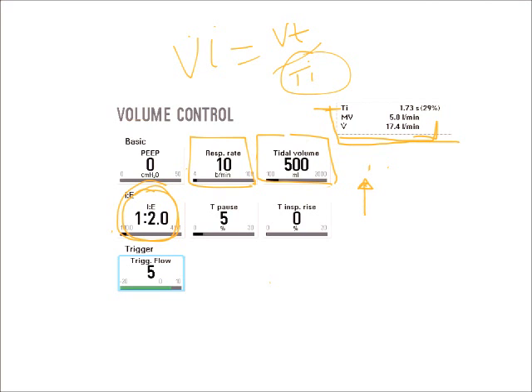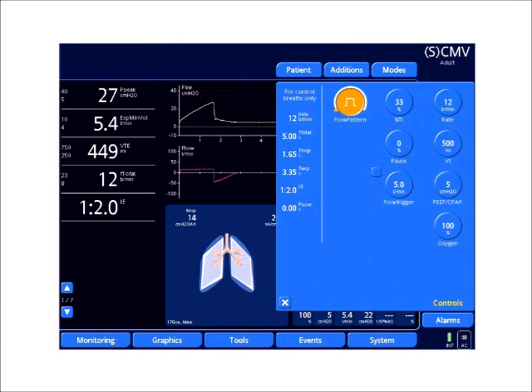So if I want to increase my inspiratory flow with my IE ratio, what I'm going to have to do is widen out the IE ratio. So if we start at a 1:2, we're going to have to go to a 1:3 or a 1:4, and this would increase my inspiratory flow.